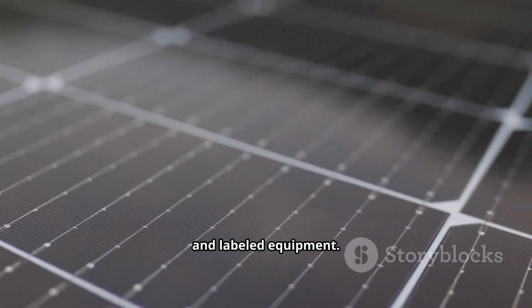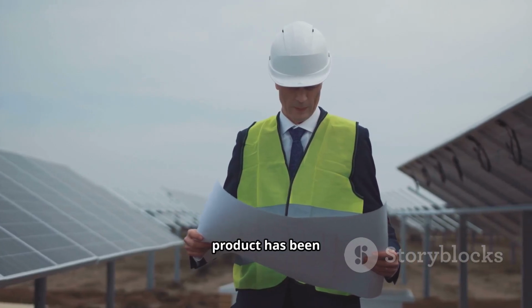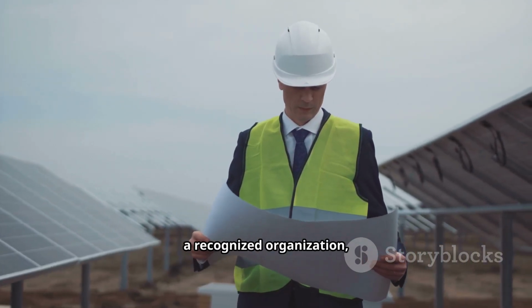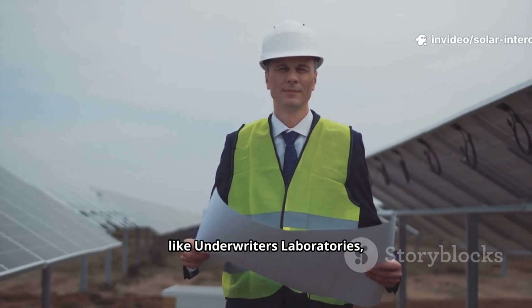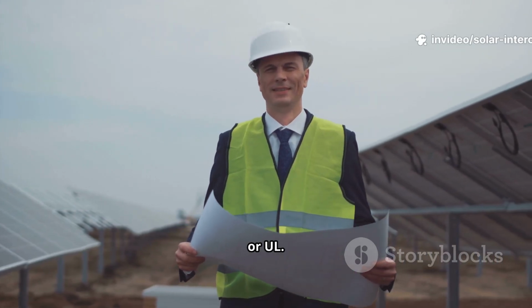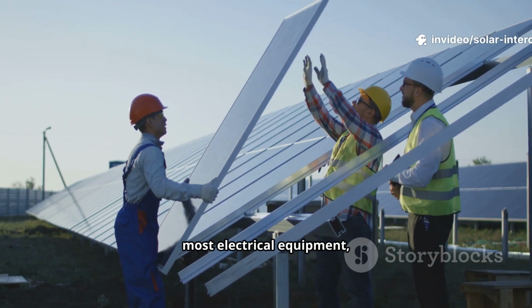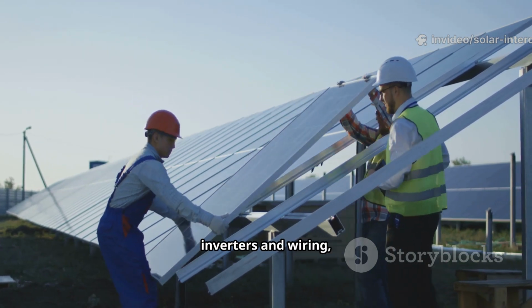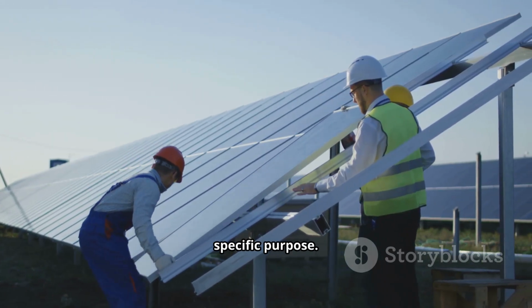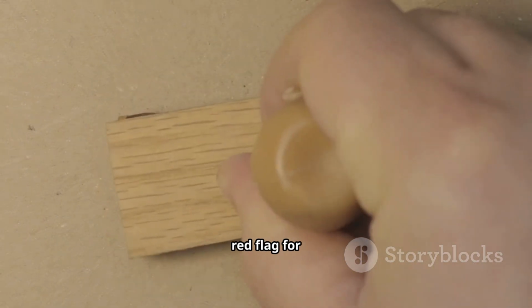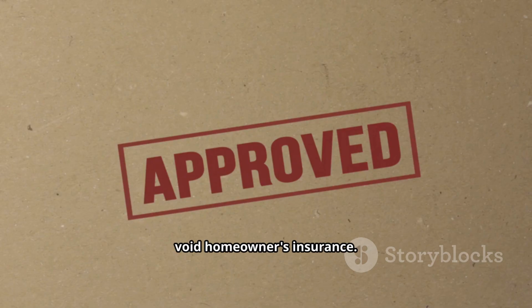Always use listed and labeled equipment. Listed means a product has been tested for safety by a recognized organization like Underwriters Laboratories or UL. The NEC requires most electrical equipment, including solar inverters and wiring, be listed for its specific purpose. Using unlisted equipment is a major red flag for inspectors and can void homeowners' insurance.